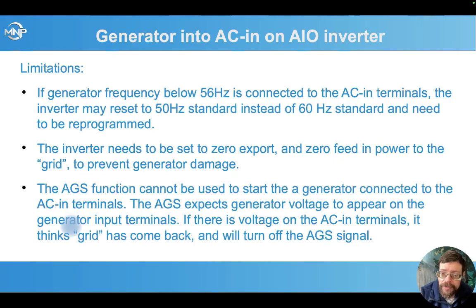That's also a sign you're overloading the generator if it does that. The inverter needs to obviously be set for 0 export and 0 feed-in power to the grid, which is now a generator, because you never want to export power into that generator. And the AGS function cannot be used to start a generator connected to the AC in terminals.